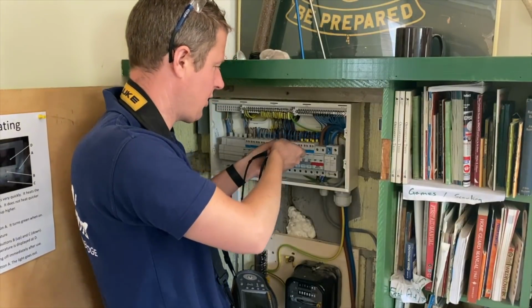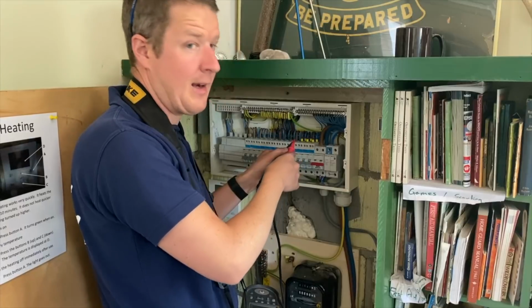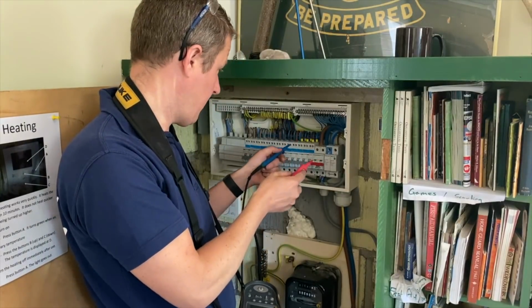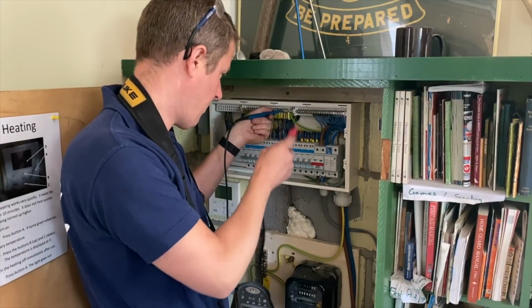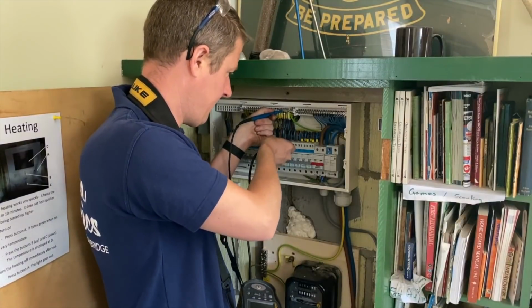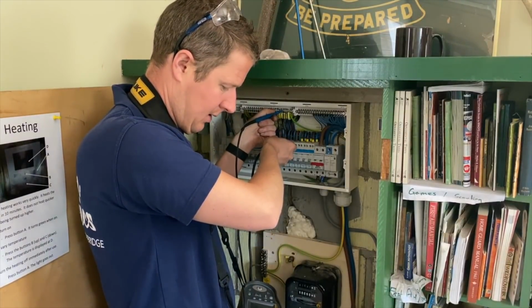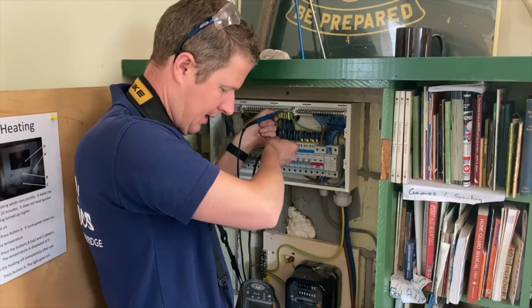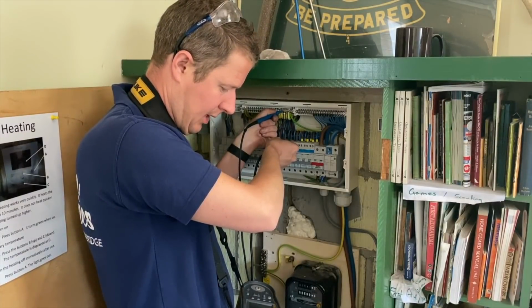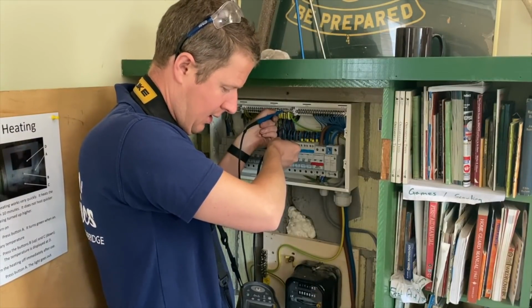Okay, live to neutral I've got a short, but that's because there's a fan isolator which is turned on at the moment. So that's reading through the internal circuitry of the fan. So that's what I meant about being in danger. If I put 500 volts live to neutral with that fan connected, it would blow the fan up.